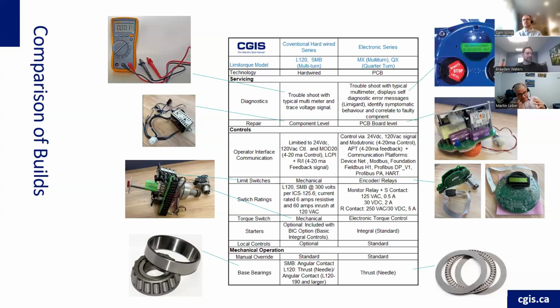If you look at the contacts on the SMB, they're big solid contacts and can carry a high current load. Meanwhile, the electronic series has a very small current load capability. The hardwired series are all mechanical switches, and the electronic series has electronic torque control. We're going to get into this a bit on the next slide or so.